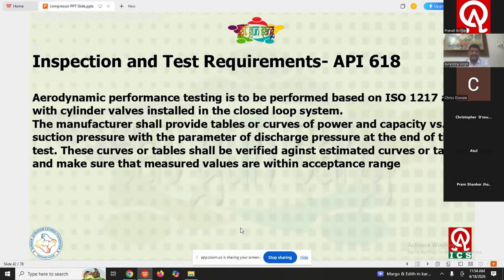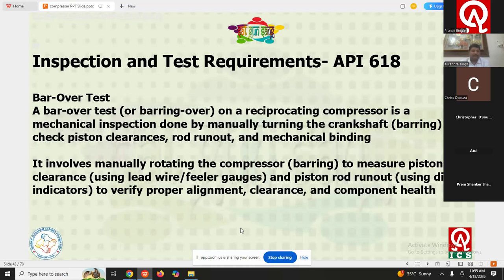So basically, it's a graphical test. First, the vendor has to plot a graph or curve as per the ISO 1217 requirement, and then you need to compare this plotted graph with the required value or the reference graph. If the plotted graph goes beyond the limit, then you can say my test result is not in line, so you can ask the vendor to correct the test. Now this is a customized bar-over test which is only applicable to the reciprocating type compressor.